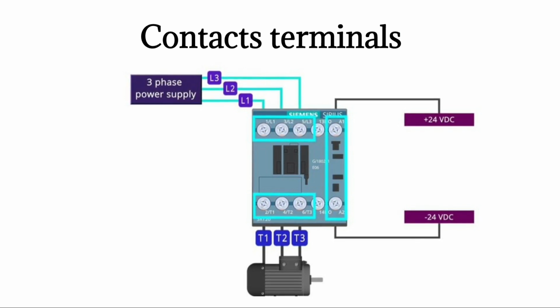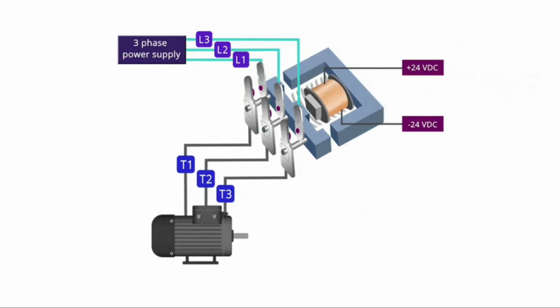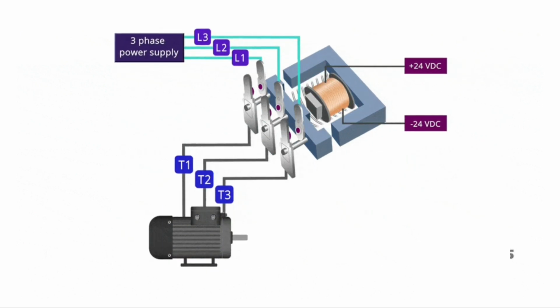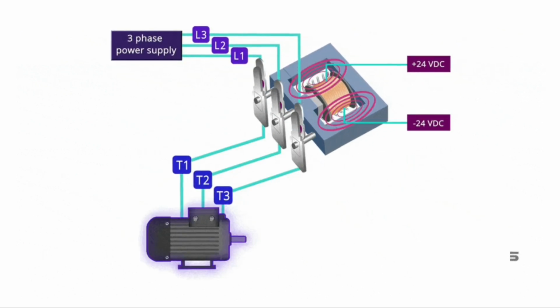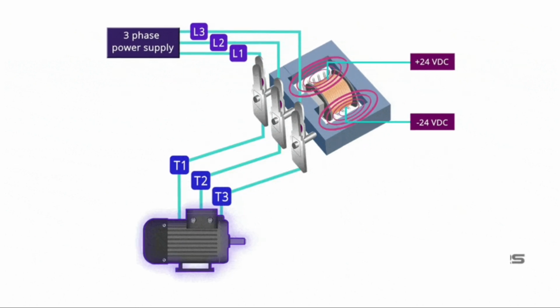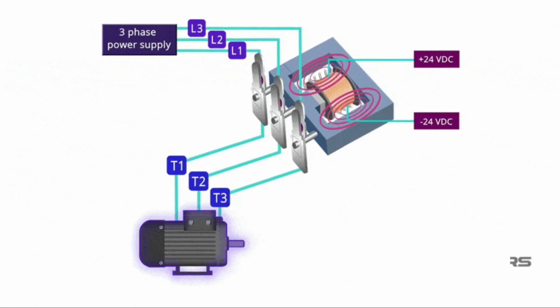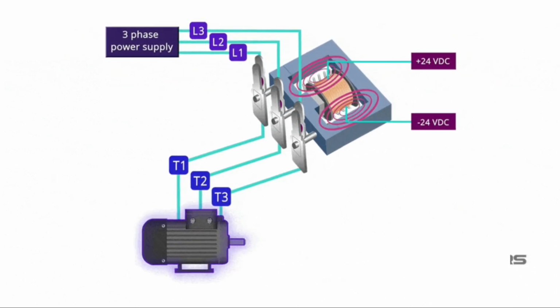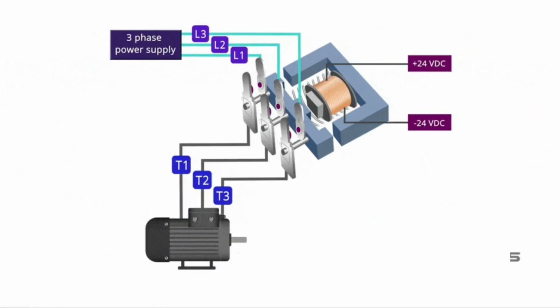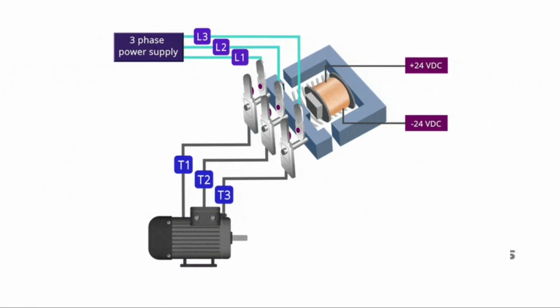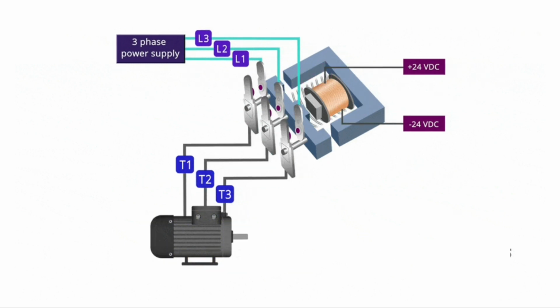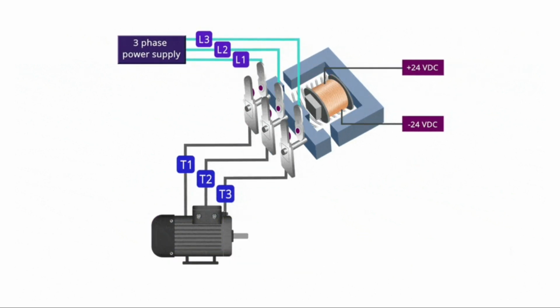contactor. The L1 contact connects to the T1 contact, the L2 contact connects to the T2 contact, and the L3 contact connects to the T3 contact. All of my contactor's contacts are normally open. With the coil not energized, the device connected to the T1, T2, and T3 terminals does not have power. When the coil is energized, the device will now have power.